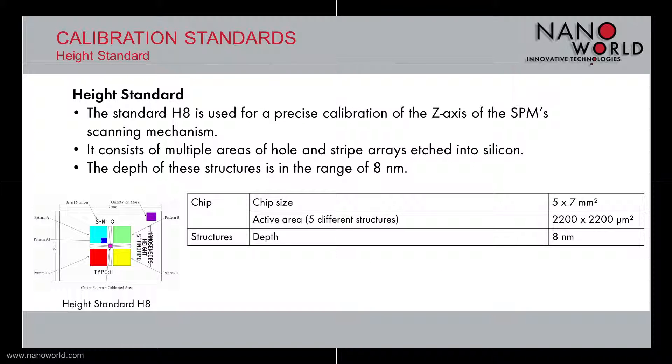The second category of calibration standards is the height standard, called H8. It is designed for a very precise calibration of the Z-axis of the scanning mechanism of SPM and AFM systems.